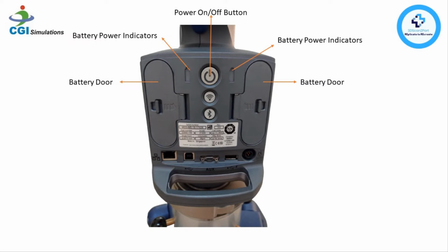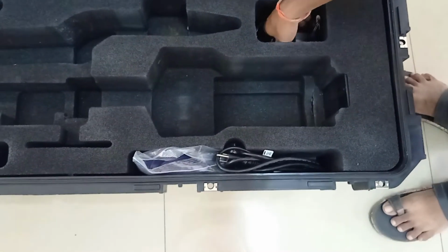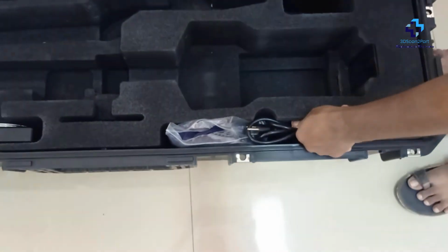So we can also see the battery power indicators. So you will see the following when a battery is installed. A red color indicates that there is no charging. Yellow indicates it is 50% charged and green indicates that the batteries are 100% charged. The color will change as the charge rises and lowers. So a solid light indicates that the batteries are not being charged and blinking indicates that the batteries are being charged. Let us see the wiring of the quantum arm.